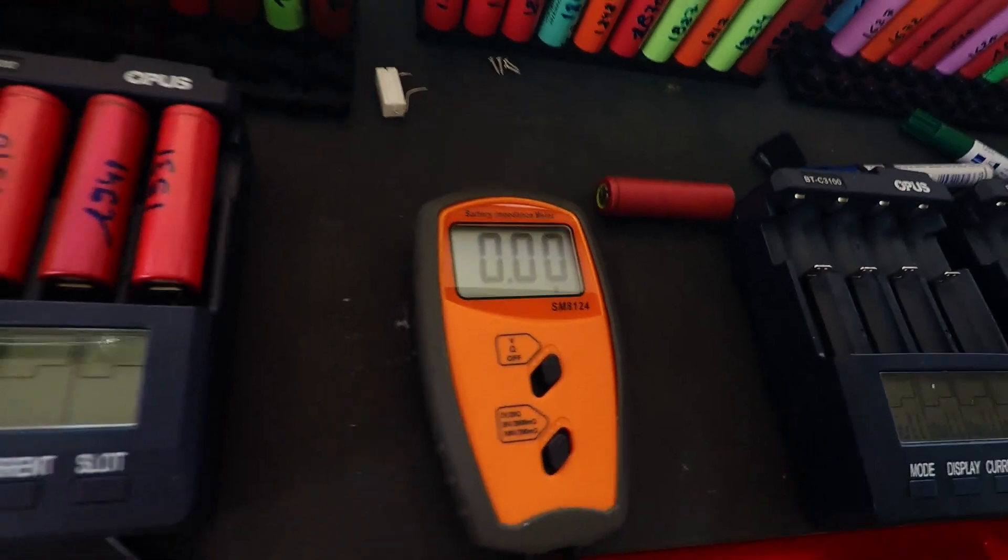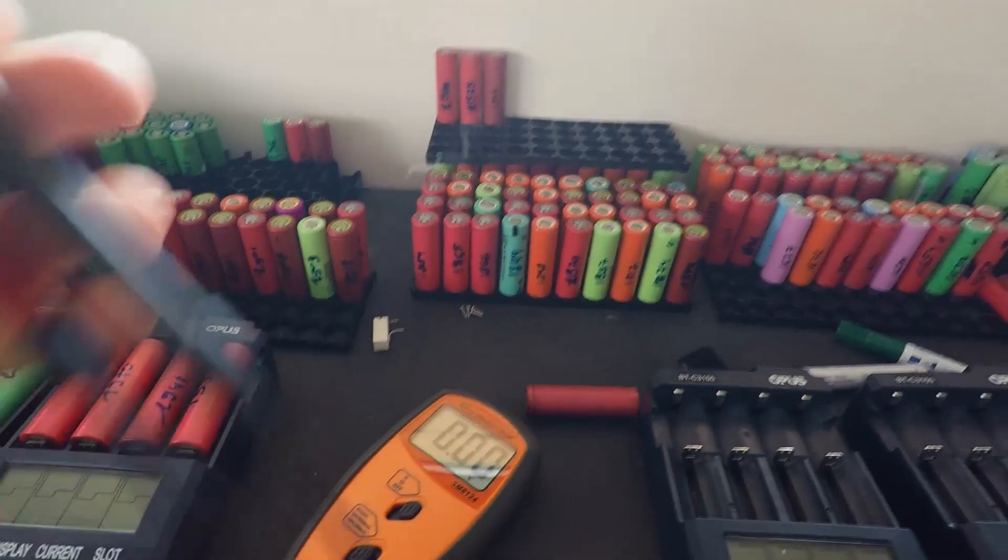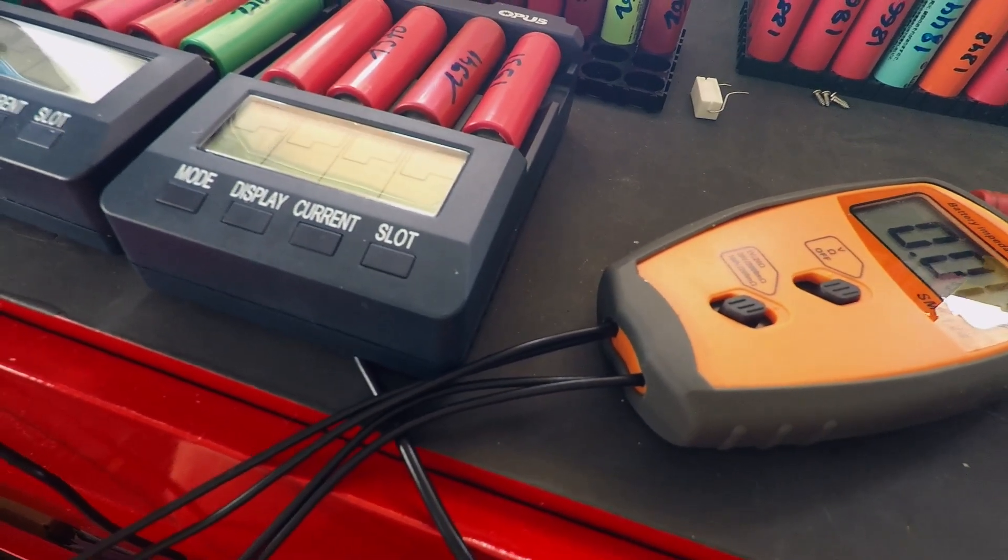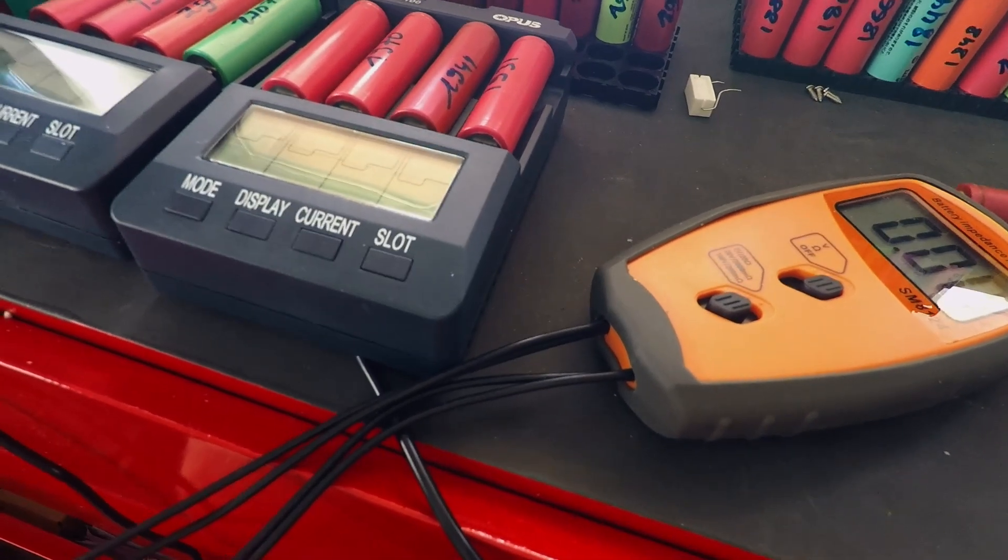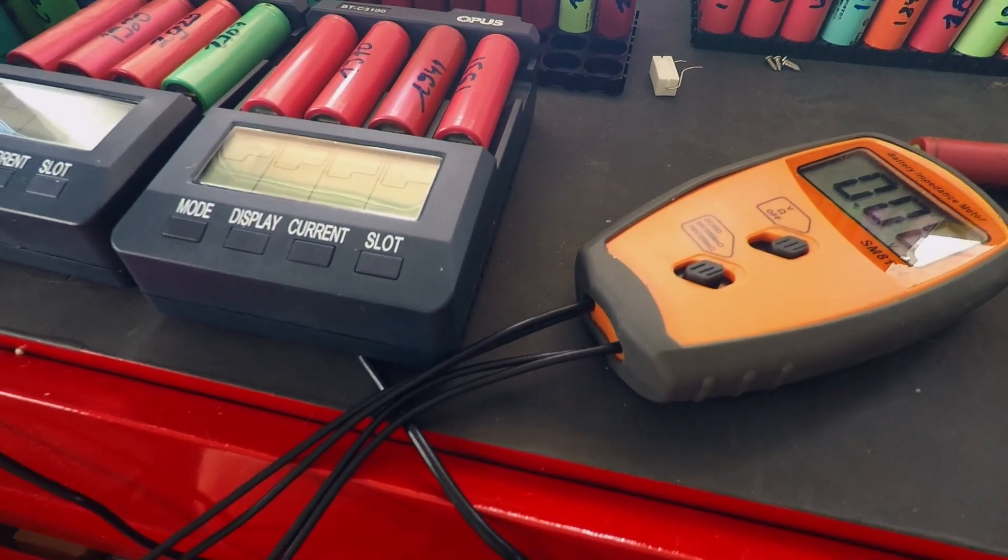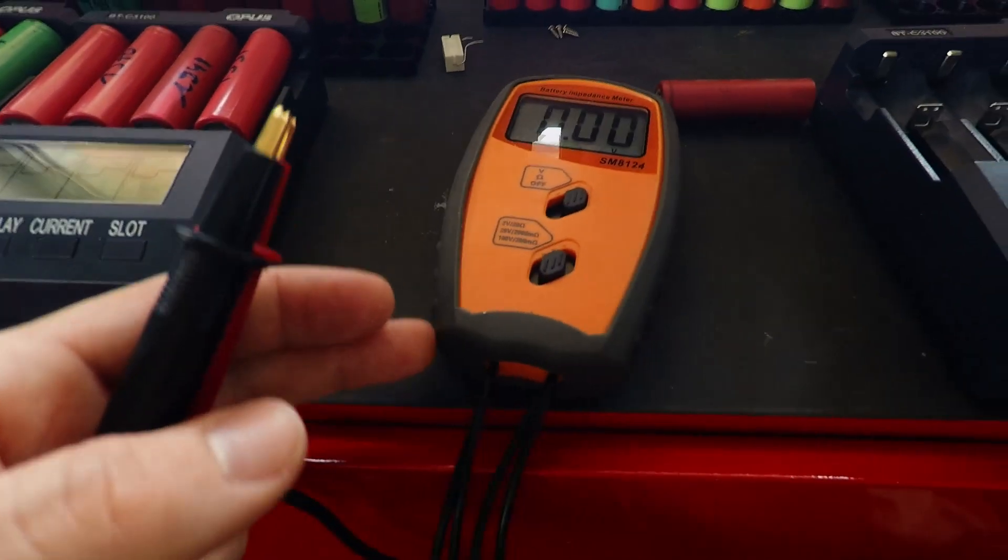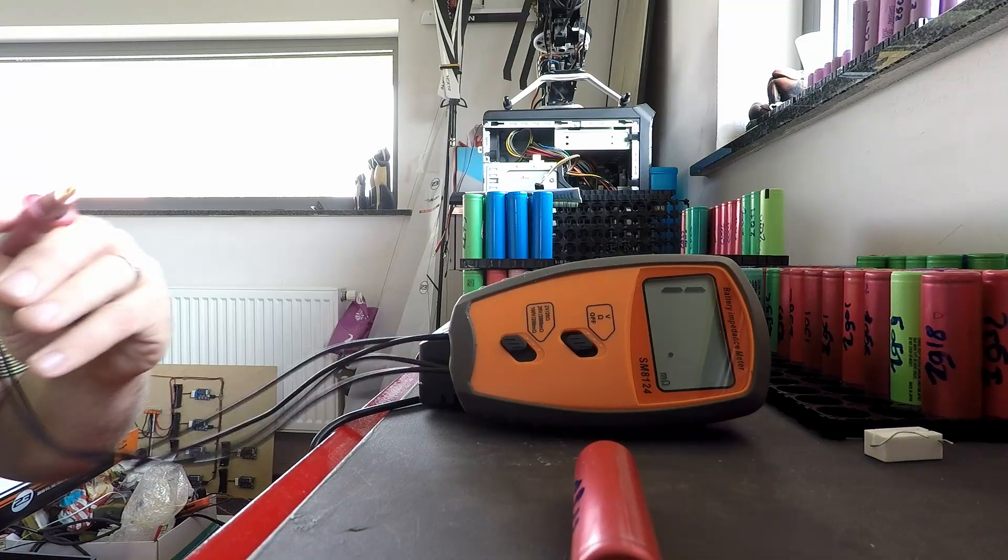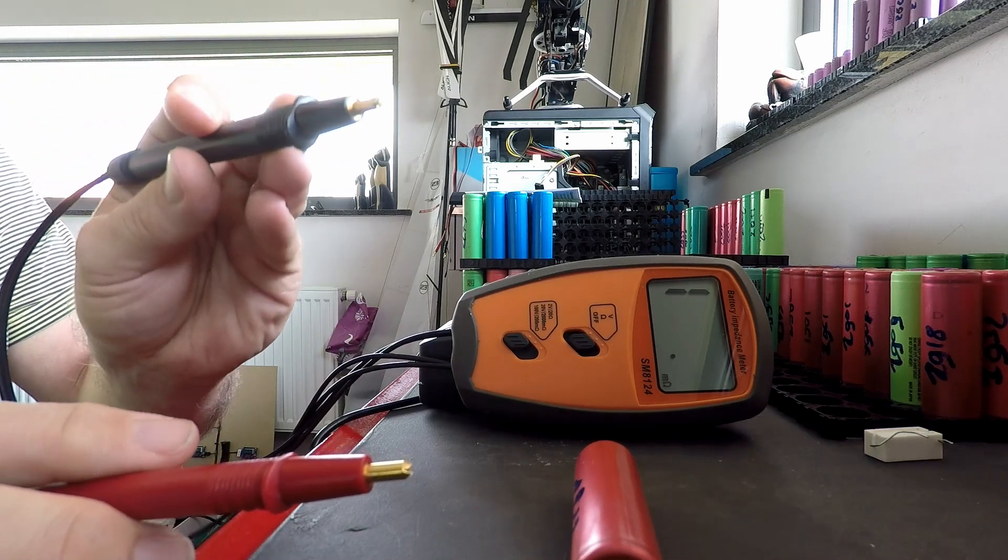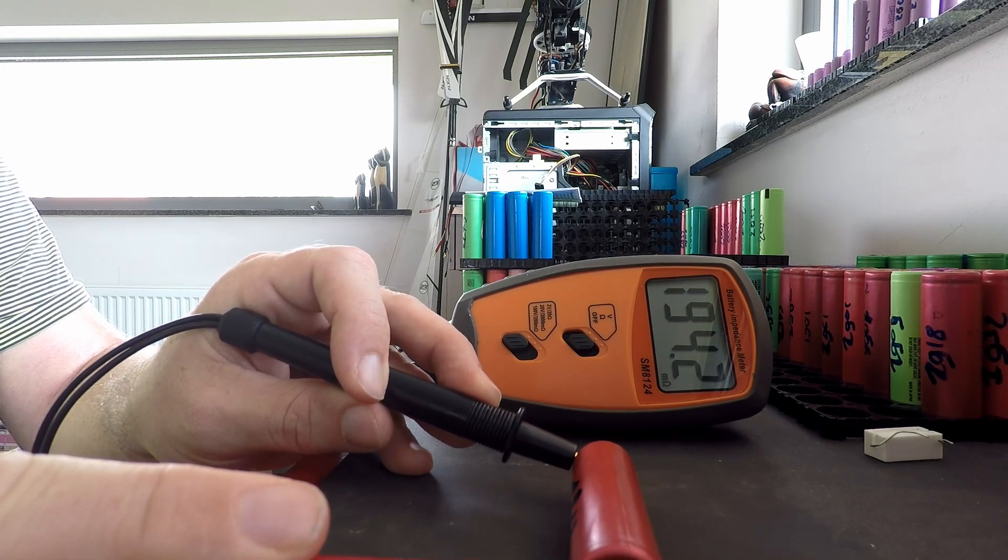What's also special about this meter is that it takes measurement through a double cable measurement. For the impedance measuring, one of the two cables is used for the voltage and the other one is used for the impedance, so in that way it can be measured in one step. We have a red and a black one. The black is for the negative, the red is for the positive.